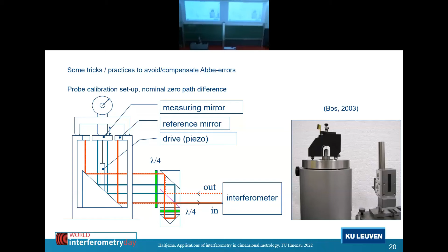then this is a typical result, and then I come to one of the issues of interferometry, and that is the periodic errors. This is the calibration of a linear gauge, an LVDT, an inductive probe, and you see small deviations with a period of a half wavelength, and that is typical for any interferometry system. You don't want that, but there are several ways to deal with it, and the first way is just accept it. Yeah, it is that way. Because if you get such a result, you know it is an LVDT, there's no reason why an LVDT would have this period, so you think, okay, this is the laser, and I put the average here, and this is my nonlinearity curve. I'm done, fine, no problem.